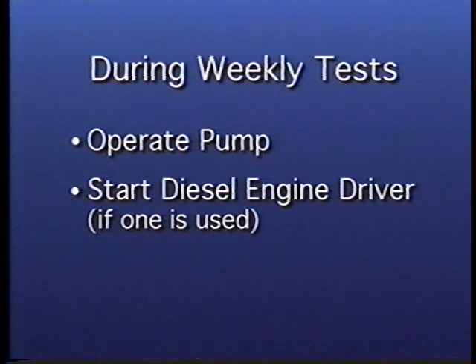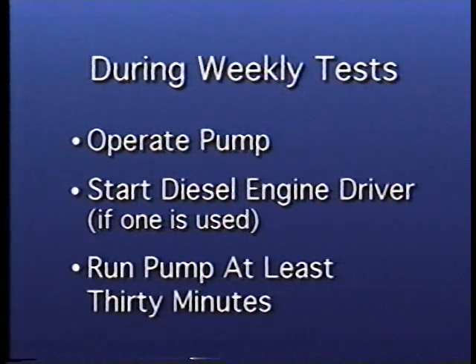If the pump has a diesel engine driver, then the engine is to be started and operated and the pump run for a minimum of 30 minutes. An automatic weekly test timer can be used for this purpose. Automatic recording devices check the performance of the pump and its driver. This can be useful to verify with your insurance carrier that proper maintenance procedures are being performed and that the equipment is performing as required.